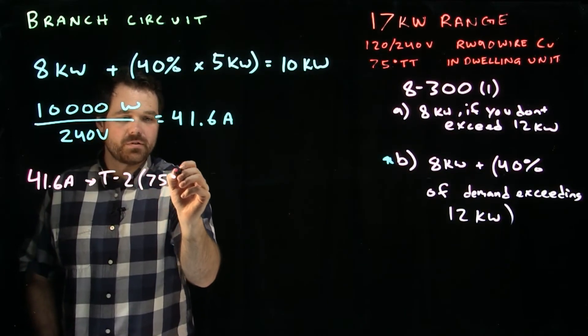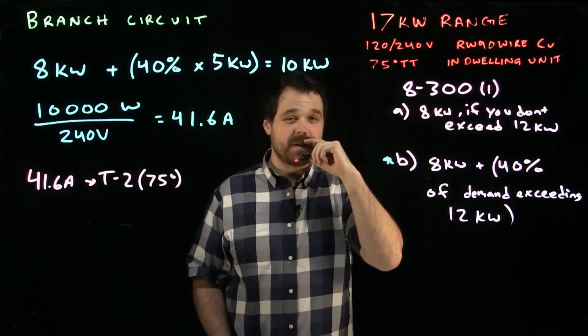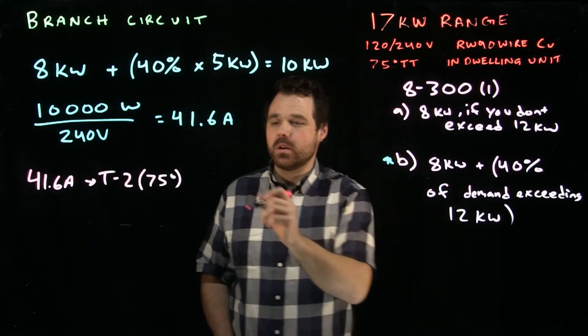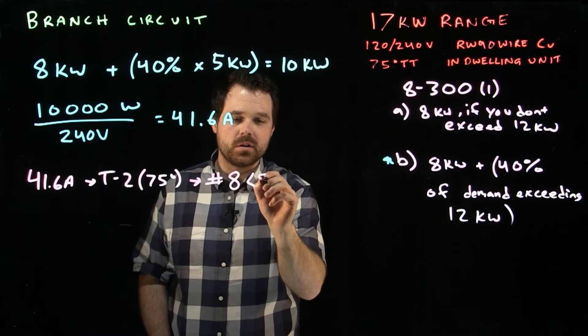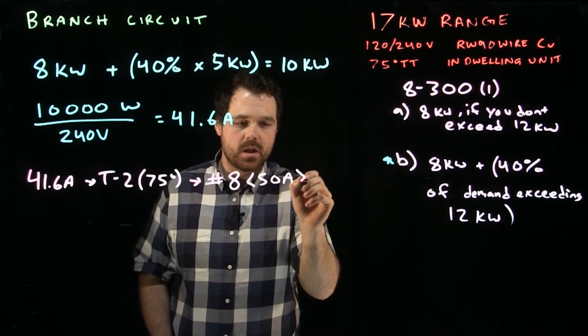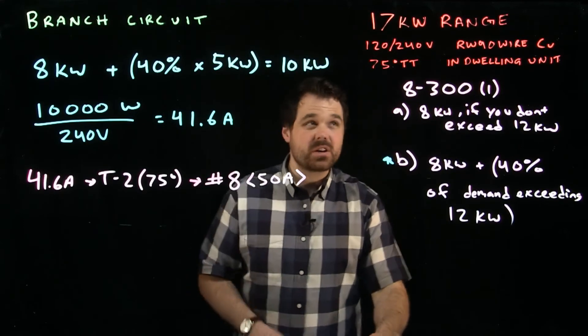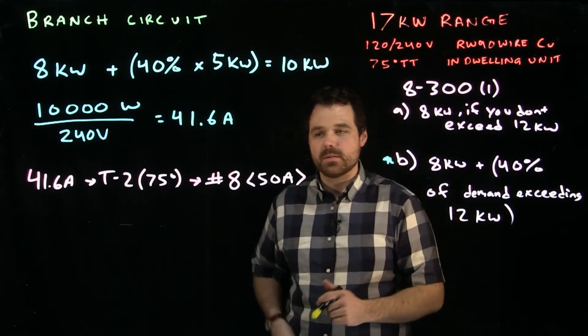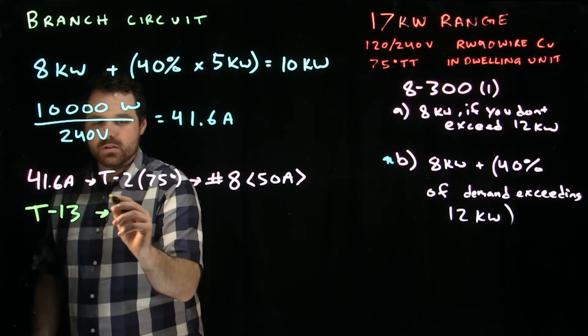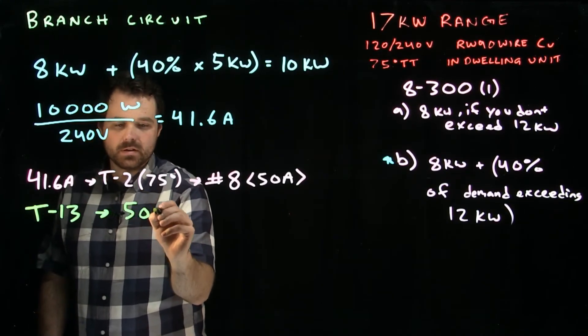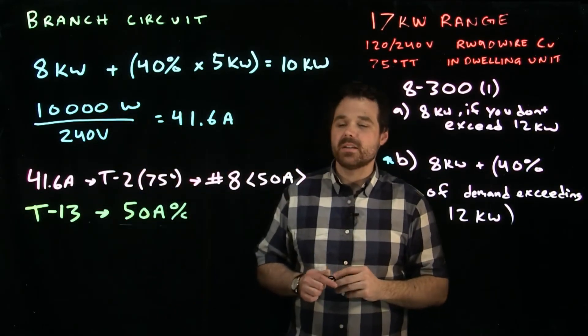In this case, we would use the 75 degree column. We're using the 75 degree column because of the 75 degree termination temperature. That gives us a number 8, which is good for 50 amps. Now that we have our conductor, that would be the size of our conductor is number 8.